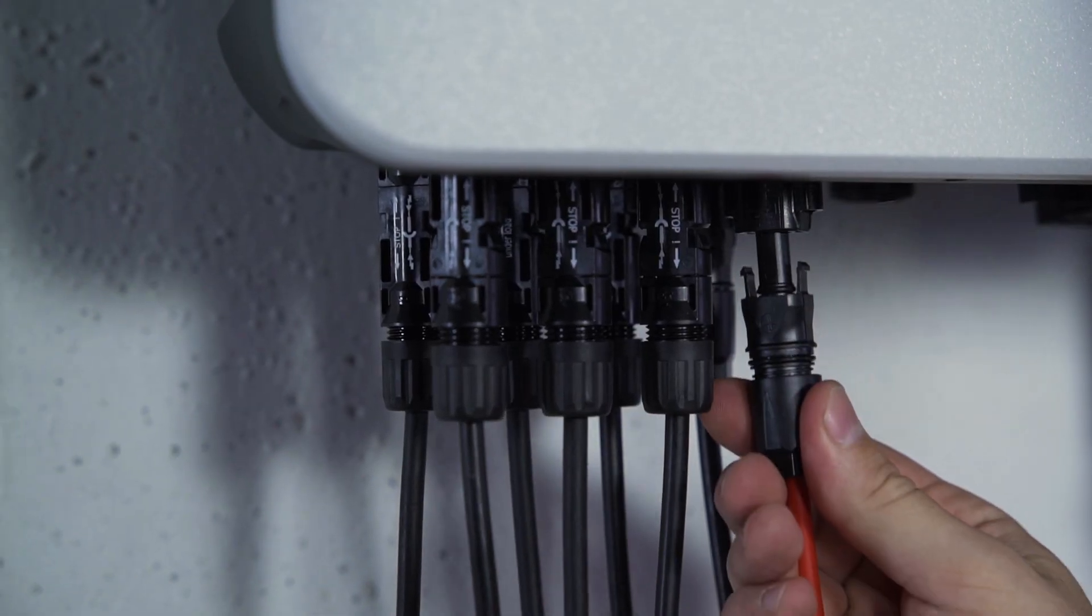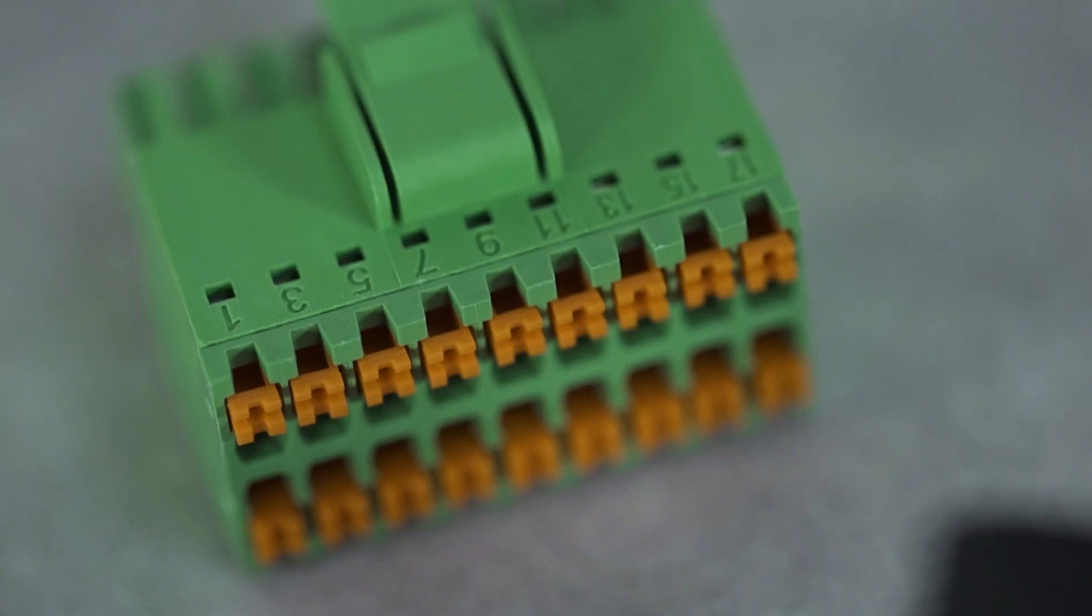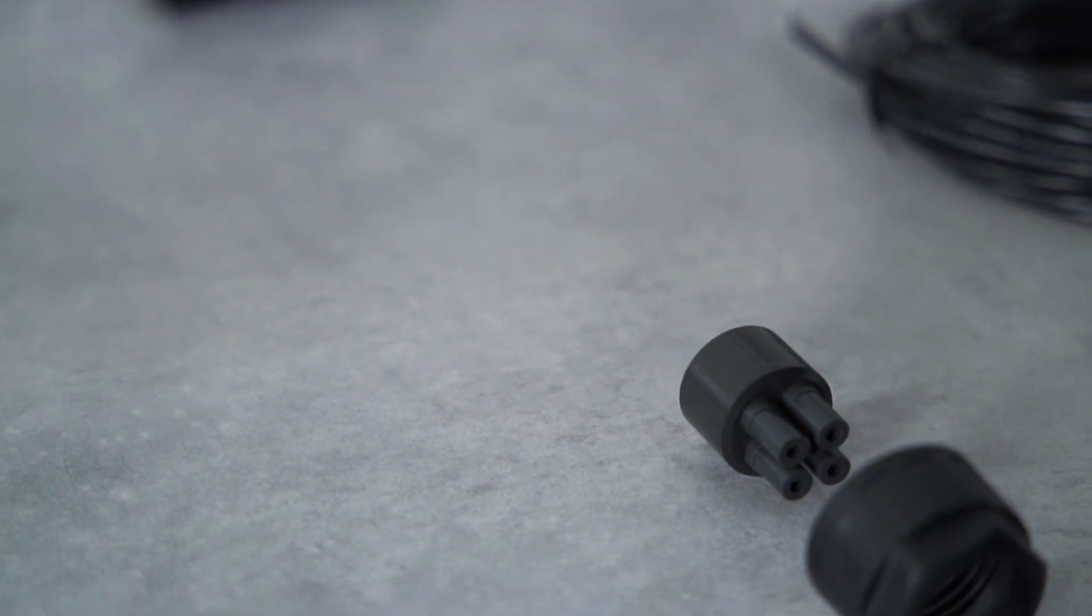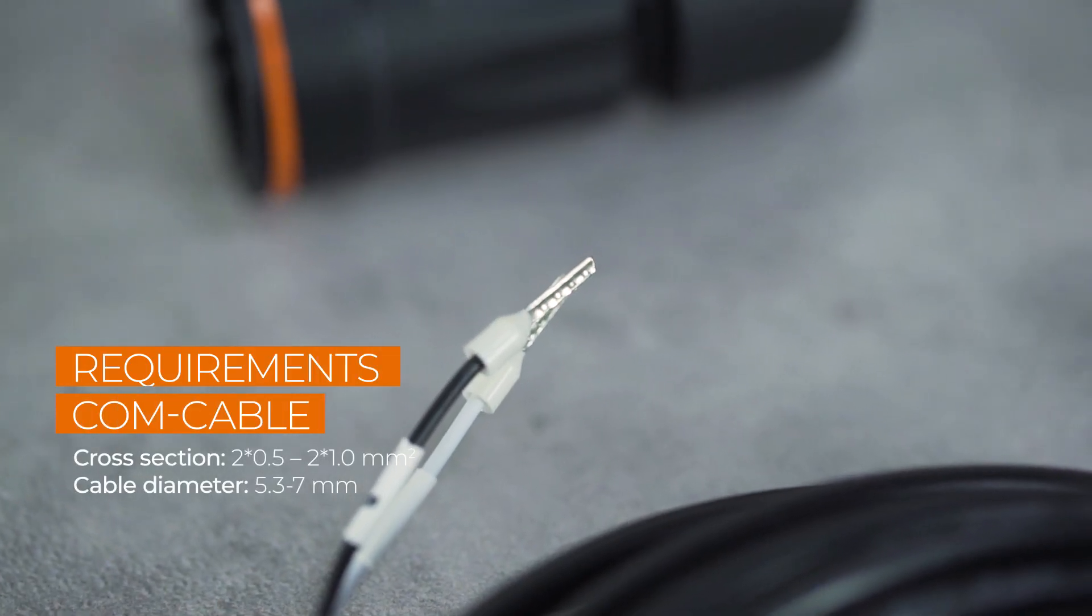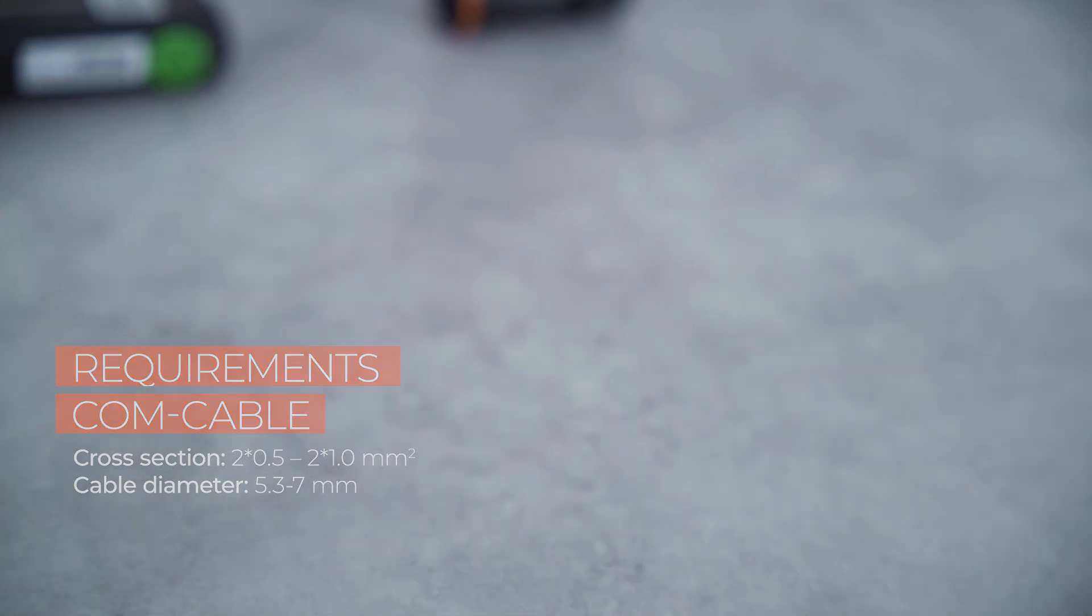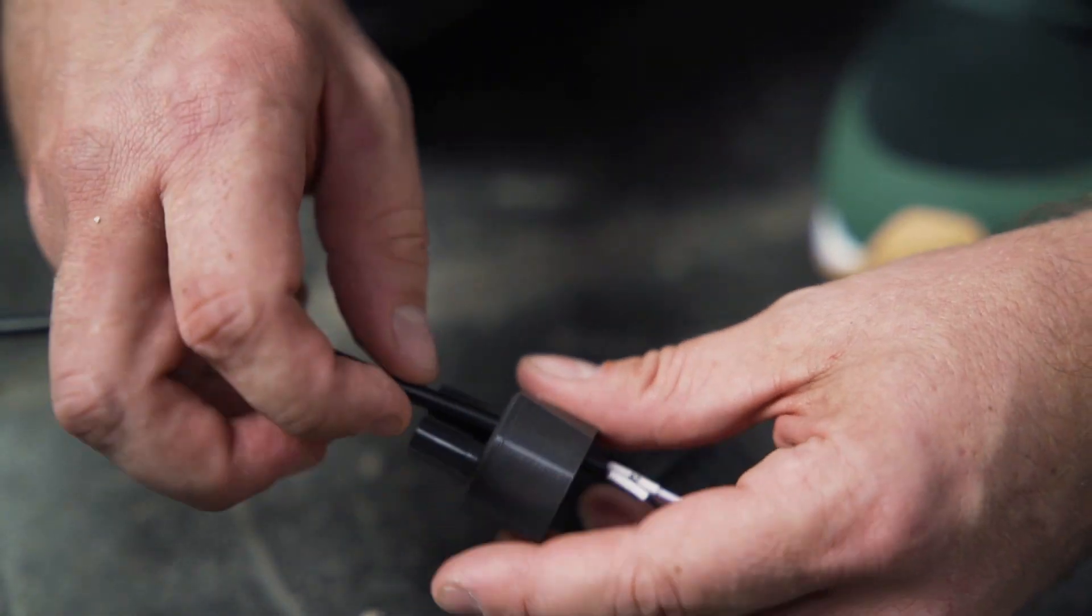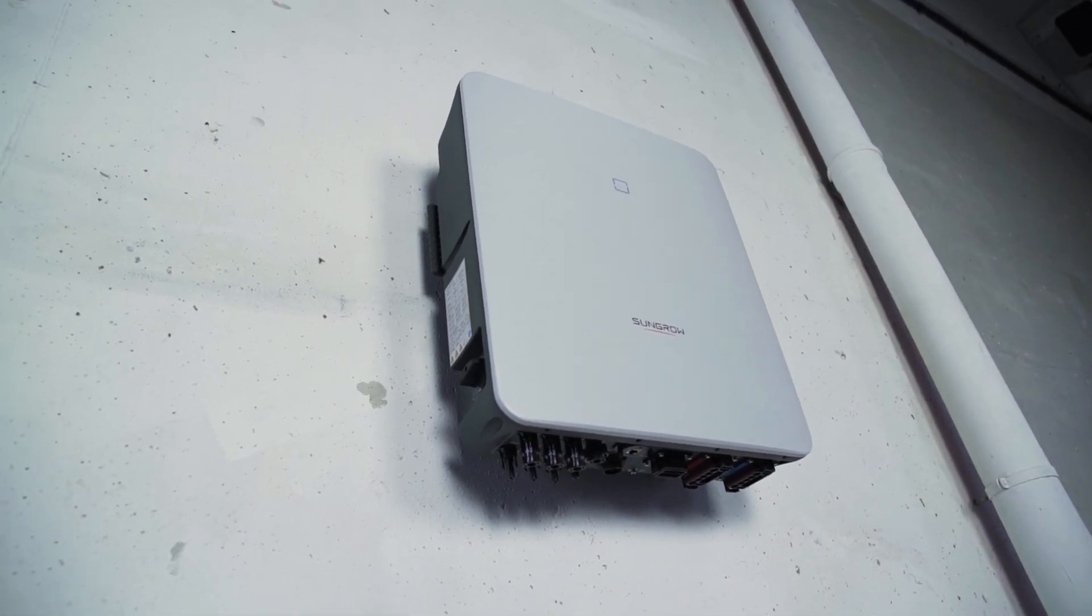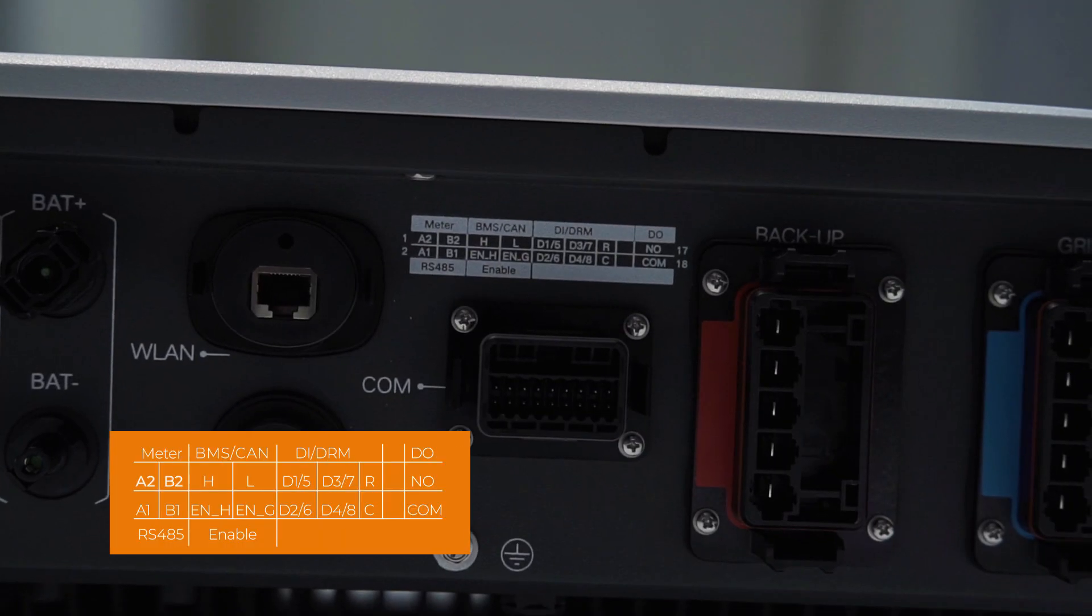Now only the communication plug is missing. The smart meter, the battery, and the heat pump for example are controlled via the communication interfaces. Remove approximately four to five centimeters of the cable sheath of the communication cables, then strip approximately five to seven millimeters of the inner cables. If necessary, you may have to fit the cables with end sleeves before you push them into the plug. At the bottom of the inverter above the connector for the communication plug, you will find a table with information about which cable has to be plugged into which port.